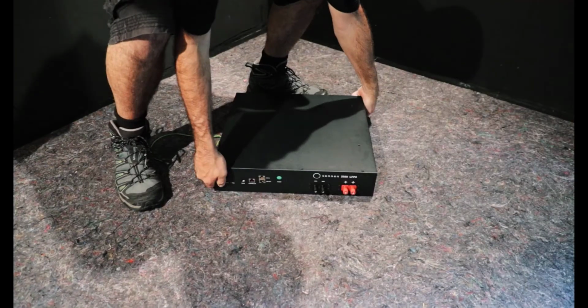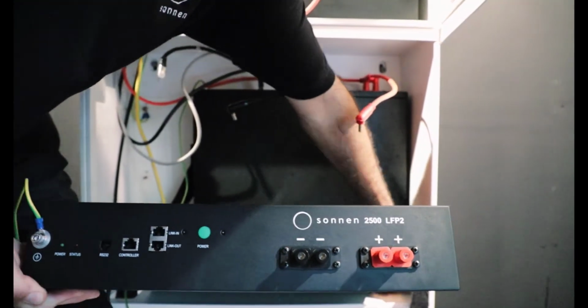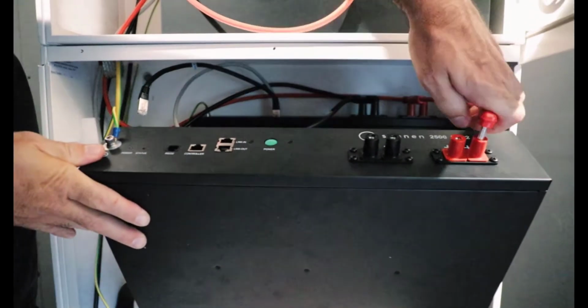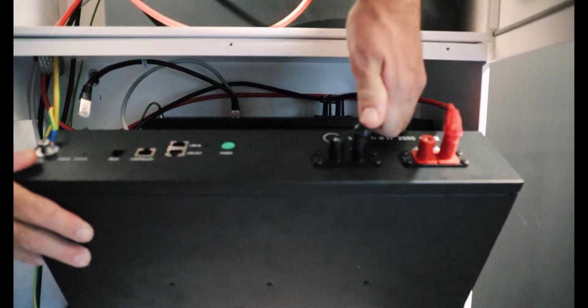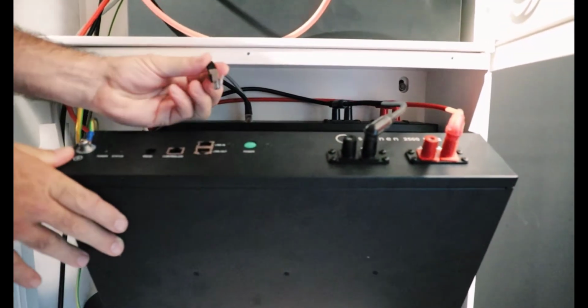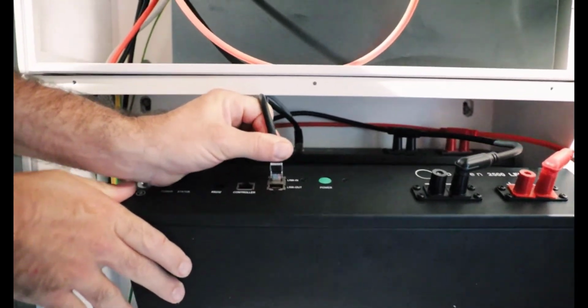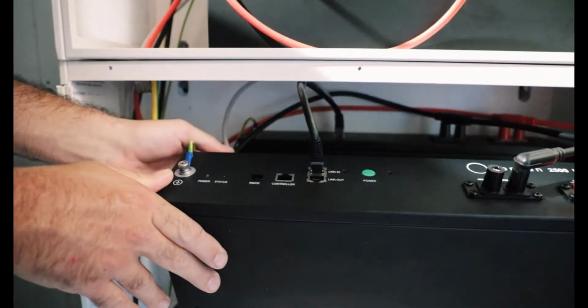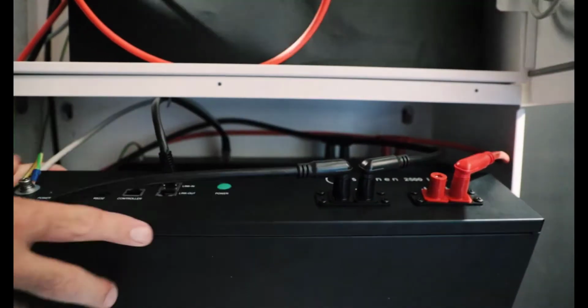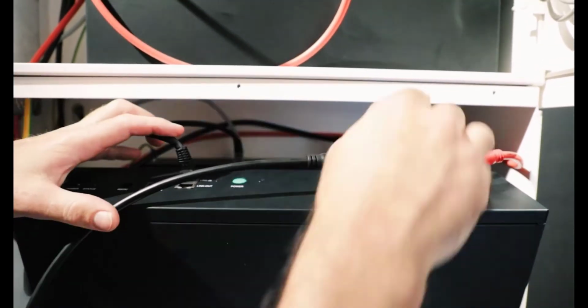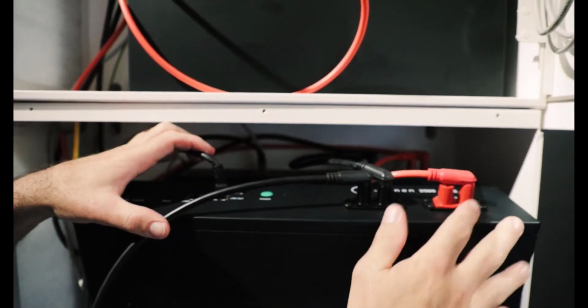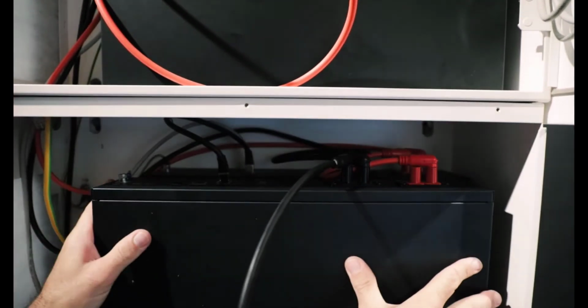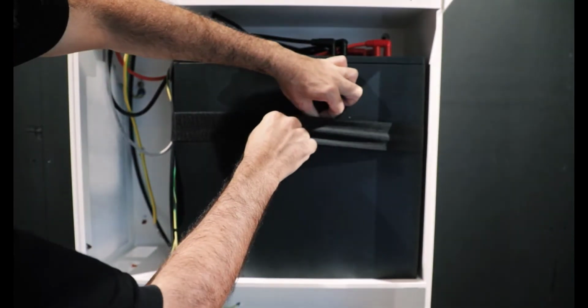And then finally take battery number 4. So as you can see, there is actually a spare position at the bottom of the extension housing. The sonnen system is able to take 6 battery modules, allowing for 15 kilowatt hours of total capacity. Positive in, negative in, and the final CAN bus connection going into the in position. Now, as this is the last battery, we also then take the negative from the main head unit to this. So although the batteries are actually wired in parallel, the initial positive goes to battery number 1 and the negative goes to the last battery, in this instance battery number 4.